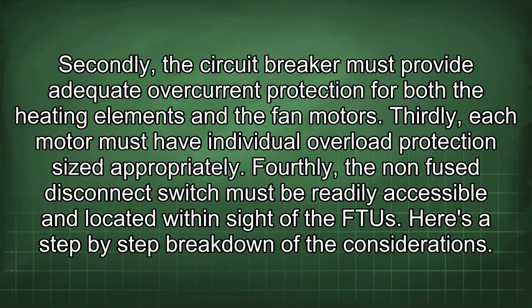Thirdly, each motor must have individual overload protection sized appropriately. Fourthly, the non-fused disconnect switch must be readily accessible and located within sight of the FTU. Here is a step-by-step breakdown of the considerations.